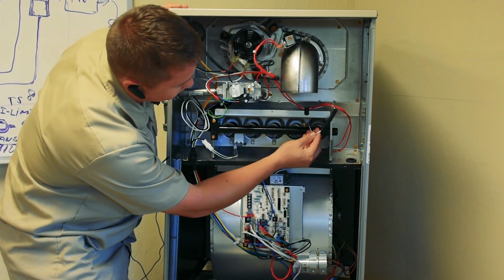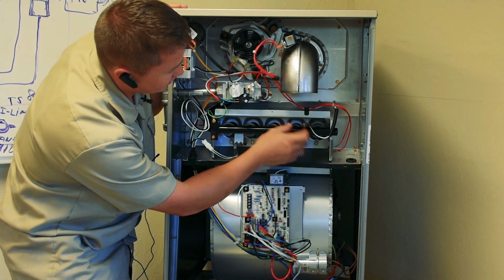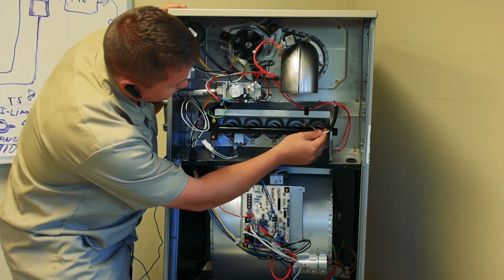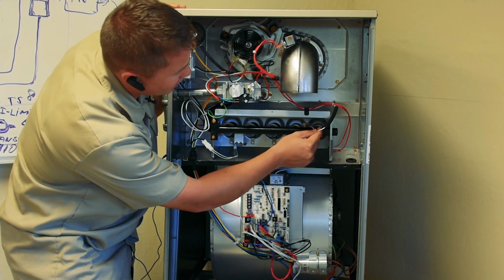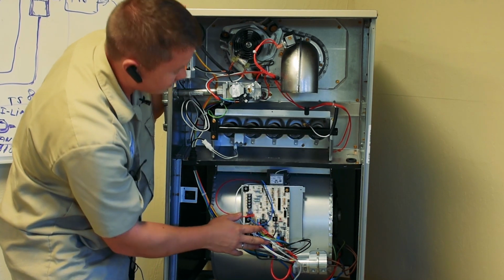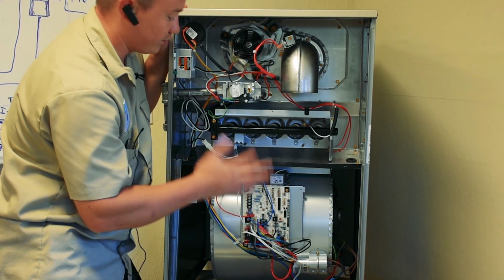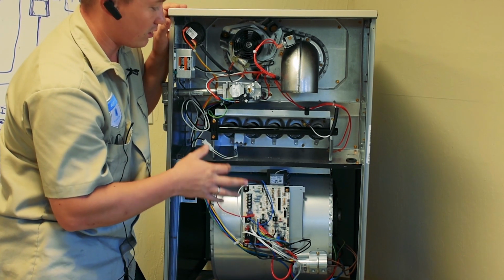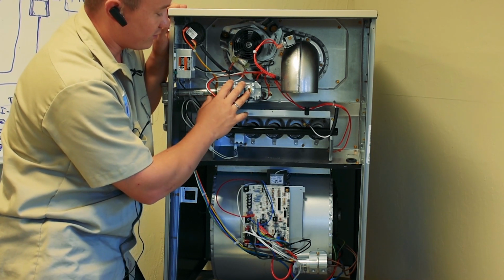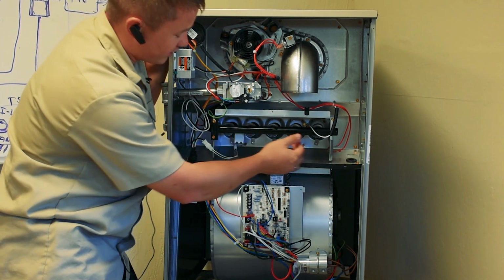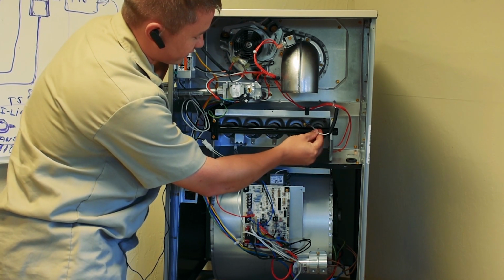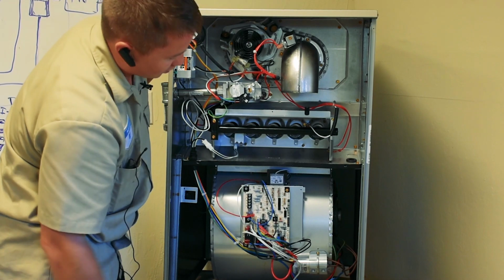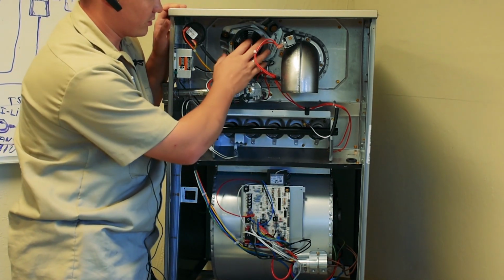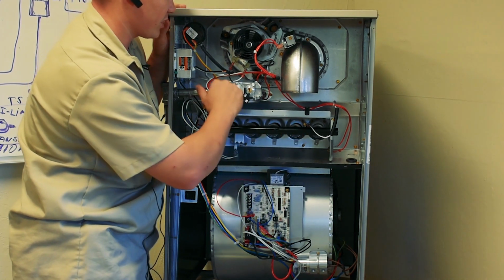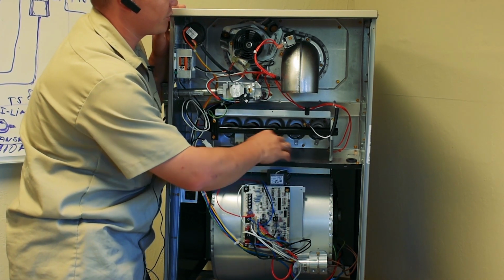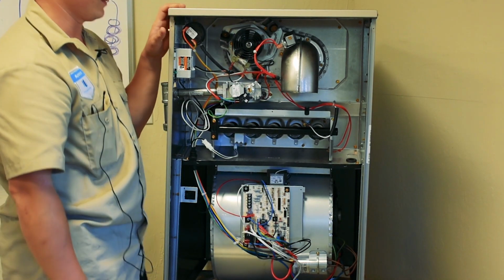And here, this wire, actually, here we have a flame sensor. This flame sensor will send a small amperage electricity to the control board, and it will tell the control board to keep running the gas valve. The gas valve will turn off automatically when it does not sense the flame, or if something is wrong with the flame, just like if it stops the inducer motor because it will not suck the airflow through the heat exchanger, it will stop the burning process.